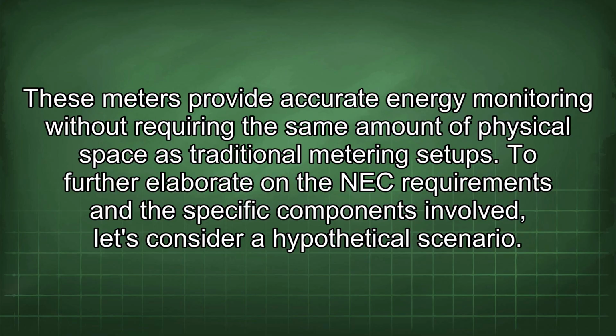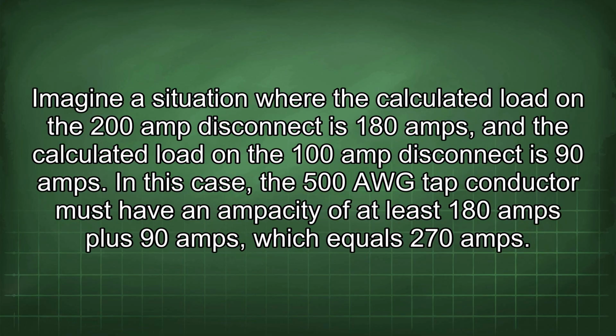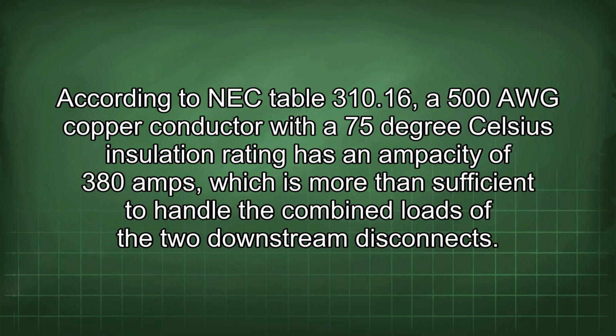To further elaborate on the NEC requirements and the specific components involved, let's consider a hypothetical scenario. Imagine a situation where the calculated load on the 200 amp disconnect is 180 amps and the calculated load on the 100 amp disconnect is 90 amps. In this case, the 500 AWG tap conductor must have an ampacity of at least 180 amps plus 90 amps, which equals 270 amps. According to NEC Table 310.16, a 500 AWG copper conductor with a 75 degrees Celsius insulation rating has an ampacity of 380 amps, which is more than sufficient to handle the combined loads of the two downstream disconnects.